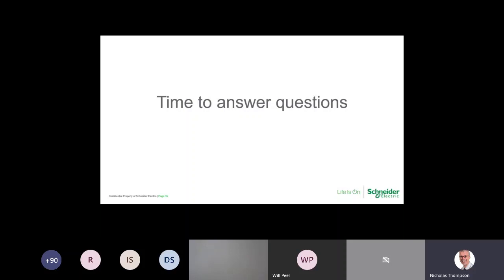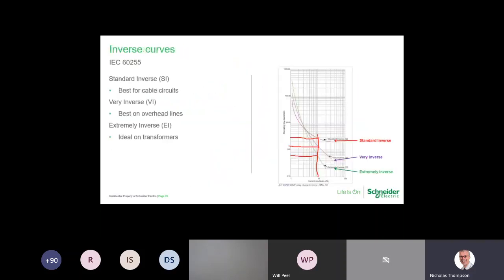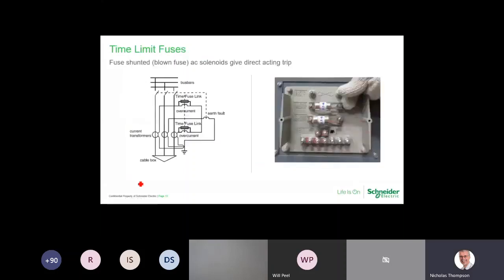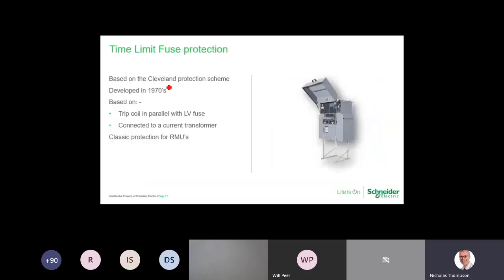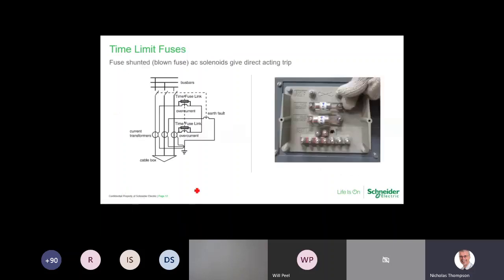So Hussein has asked a question: why do we only have 2 TLFs but 3 coils in total, on the diagram that I showed? I will try and flick back through to it. Right, so when it was first set up on the Cleveland protection scheme, and there is a paper on this, I haven't had a chance to read it. We're using 2 for overcurrent, which is acceptable. And then the 3rd coil for earth fault is deemed to cover all scenarios of earth fault current. I'll try and dig out the paper and post it up as a technical explanation as to why that is going to be used.